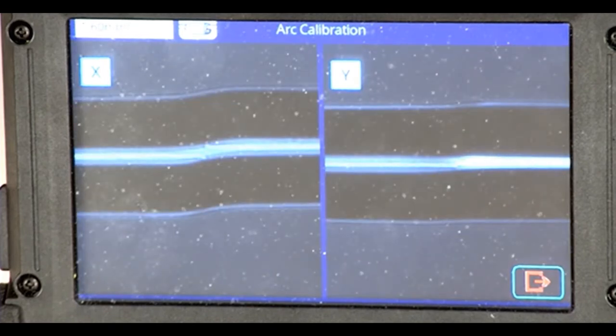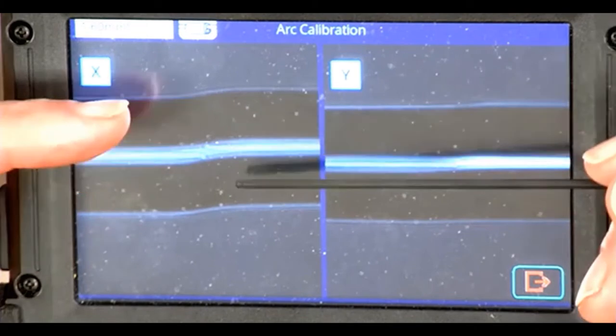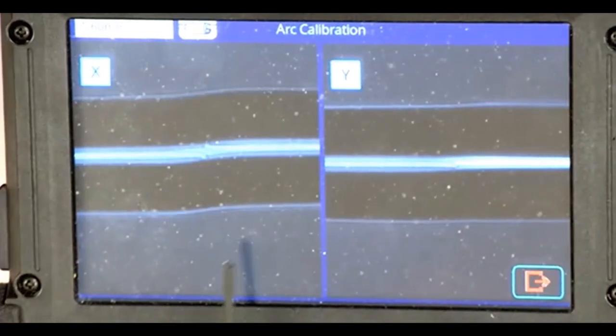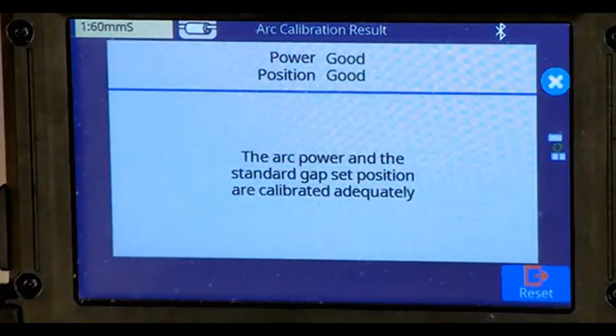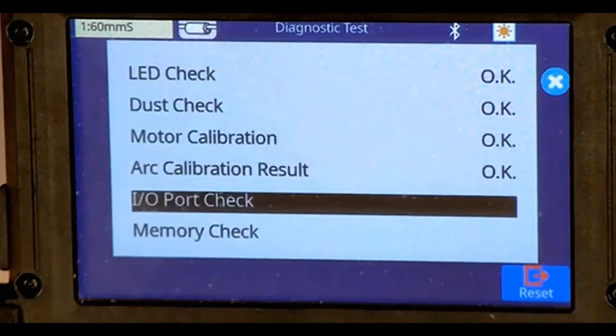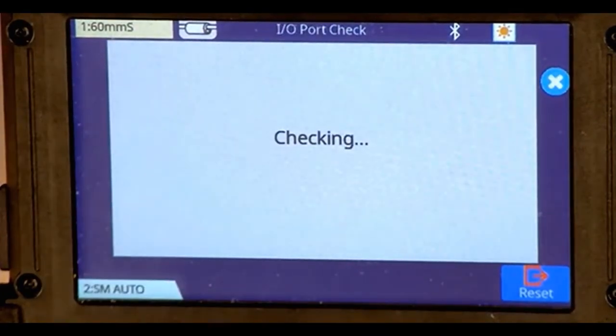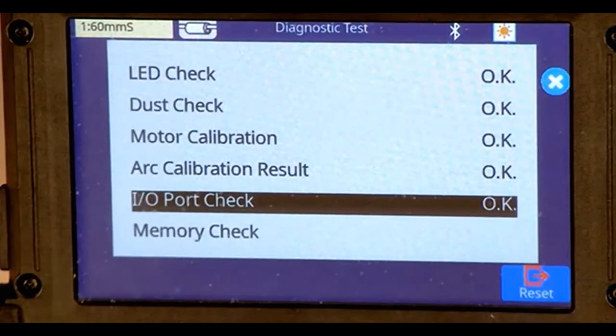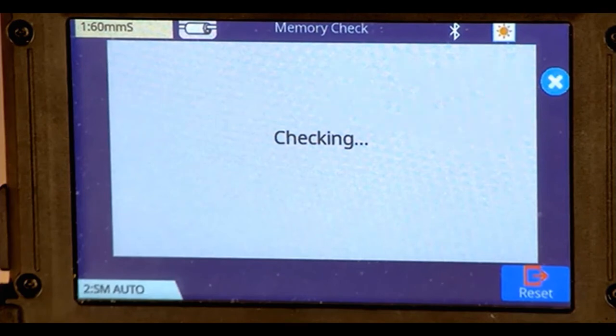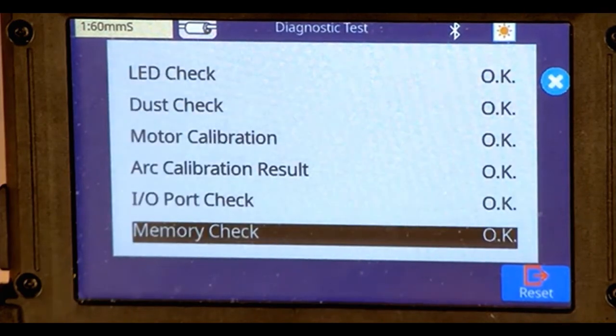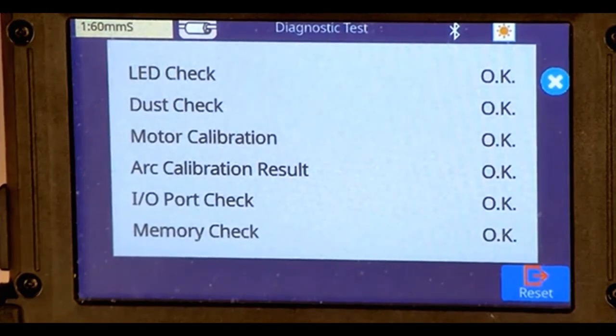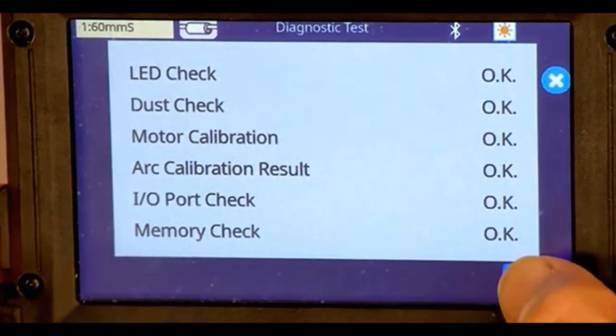And it's almost done. But you can see it's self-centered quite a bit, because when the glass gets hot, it wants to self-center due to surface tension. So we started out with a big misalignment here, and it's a lot less than it was at the beginning. Okay, so everything was good on the arc calibration. Now it's checking the communications ports, and that's done. Now it's checking memory. So the motor calibration takes a while. That's why we recommend you only do this once a week, because just doing the arc calibration by itself once a day, that's pretty quick. All right, we're done with that.